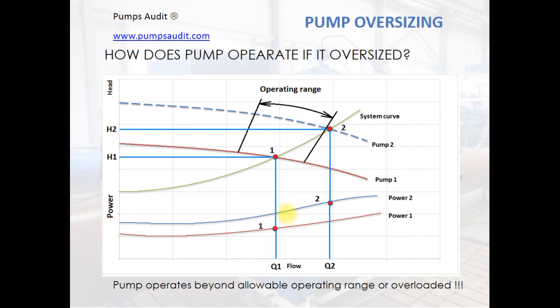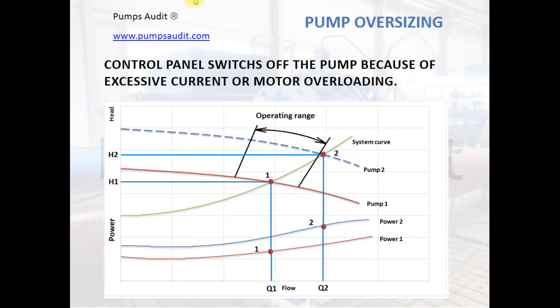The explanation is clear enough: pump number two delivers more fluid and operates with more flow, and therefore consumes more power. If the user doesn't have a flow meter, this fact is not clear. In this situation, we will have excessive current and the control panel can turn off the electric motor. If there is no control panel, or it was also selected for a more powerful motor, the motor may burn out. Very often a control panel switches off the pump because of excessive current — the electric motor doesn't have enough power, and the control panel switches off and gives an alarm.